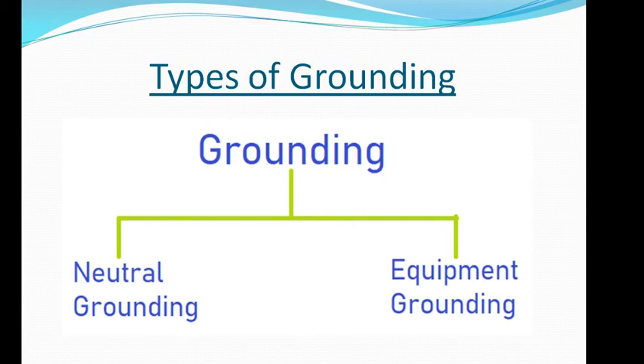There are two types of grounding systems in electrical power system networks: one is neutral grounding and another is equipment grounding. In neutral grounding, three-phase AC power systems with neutral grounding at every voltage level are used for generation, transmission, distribution, and utilization. The neutral point or star point of star-connected three-phase windings of a power transformer, generator, motor, or earthing transformer is connected to a low-resistance ground. Such a connection is called neutral grounding or neutral earthing.